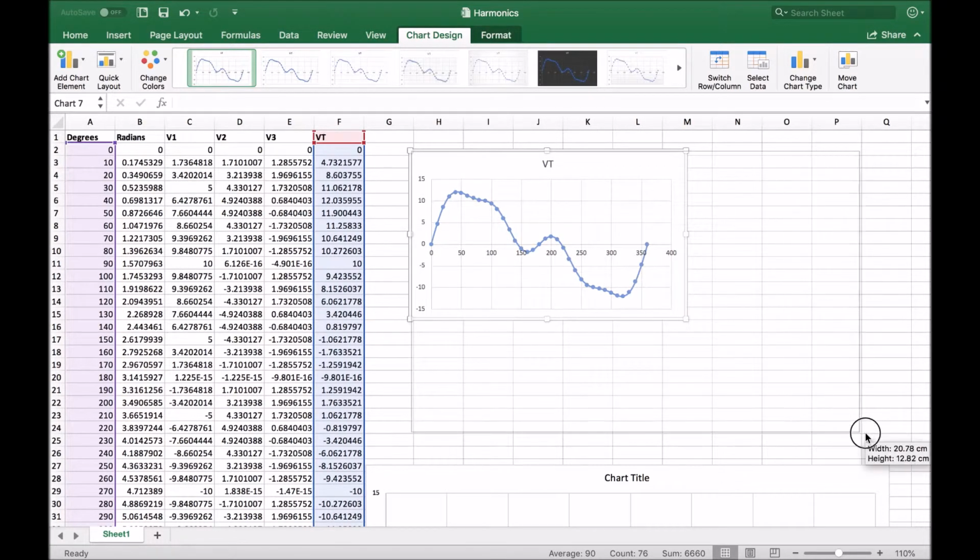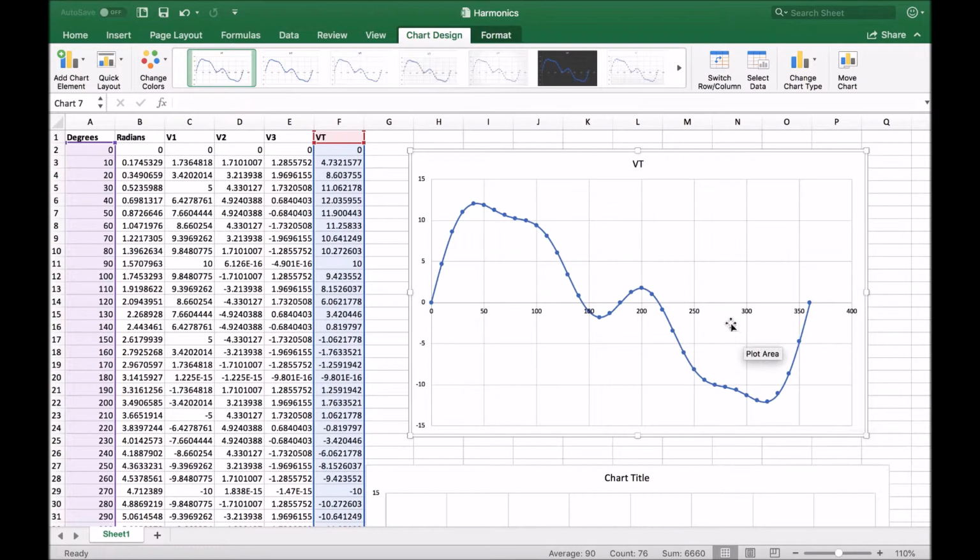Quite a bit different. And what you can see here is hopefully an illustration of one of the ways you can recognize the presence of even harmonics. And I like to call this the mirror image. So what you can see here, if I put my cursor on the 180-degree point, the halfway point in this waveform, you can see hopefully that the pattern formed by the waveform has a mirror image in the second half.